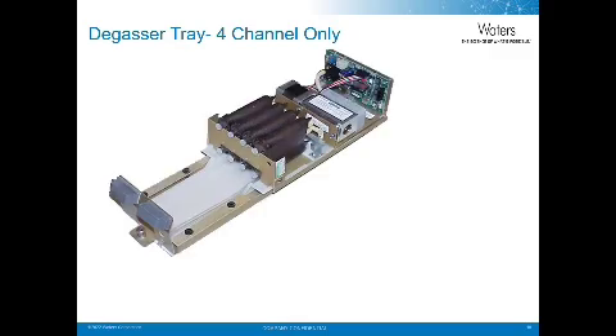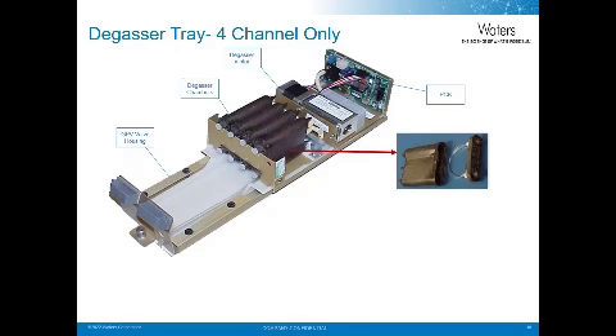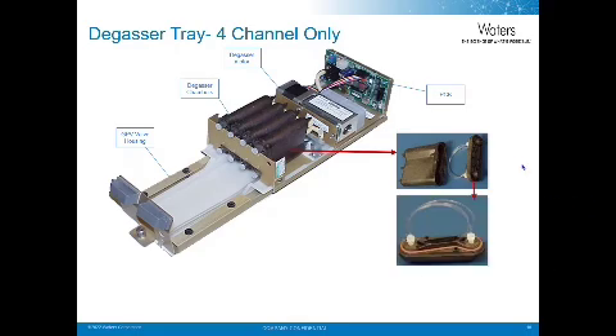Here is the degasser tray. Here we have the GPV valve housing, degasser chambers, degasser motor, and PCB. If you were to look inside of the degasser chamber, it would look like this. This is the semi-permeable membrane that the mobile phases pass through. You do not need to replace all of the chambers if one is bad. You can swap them out to isolate the bad chamber as well.